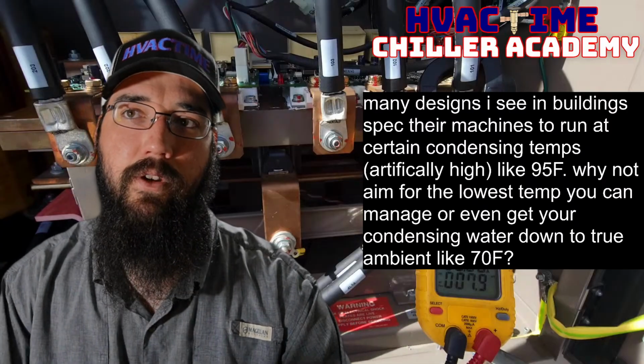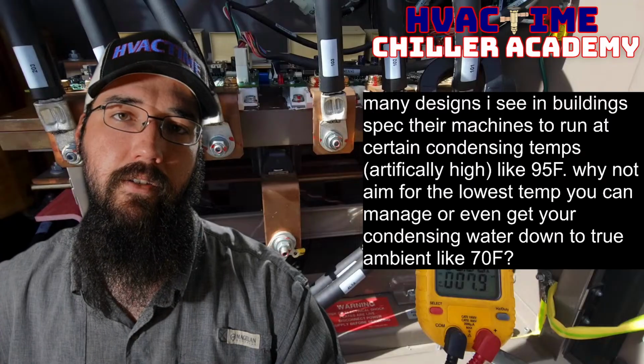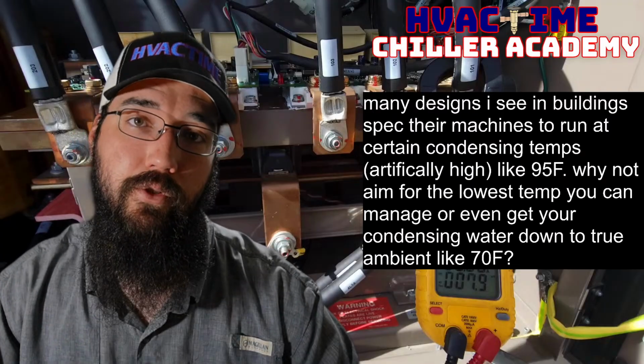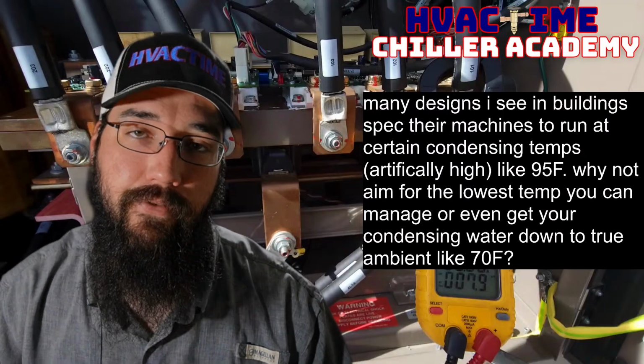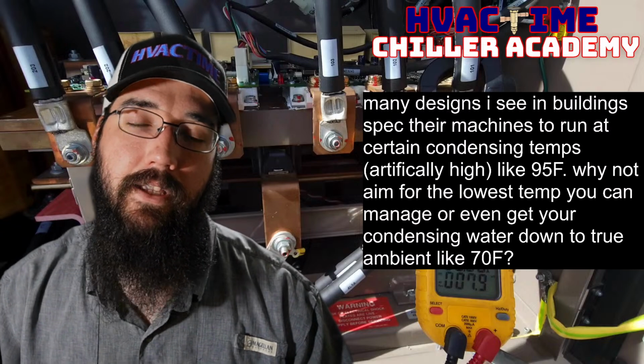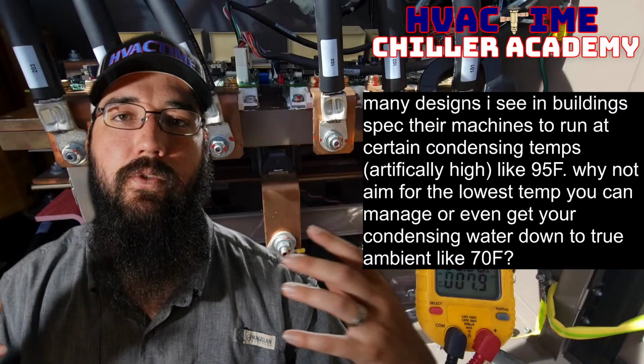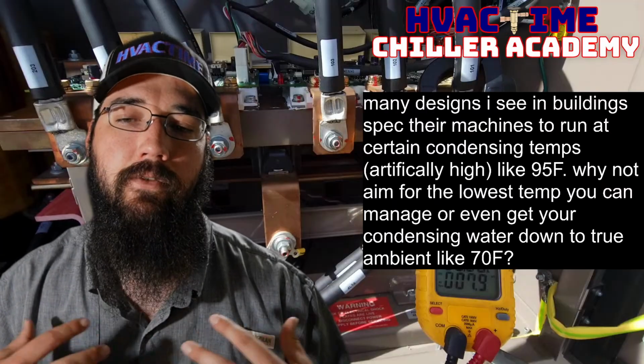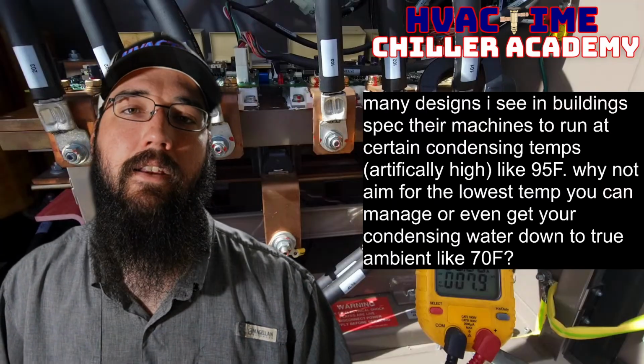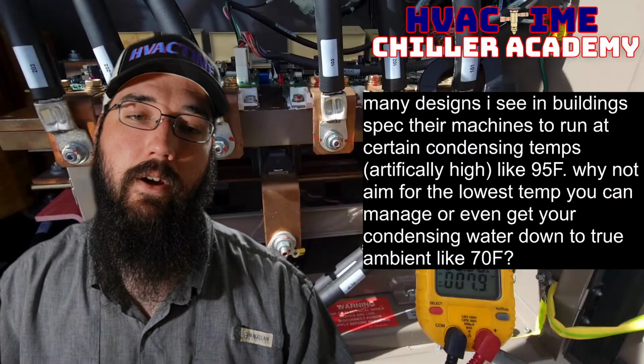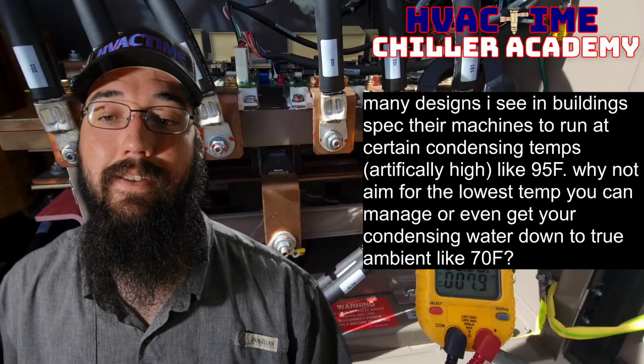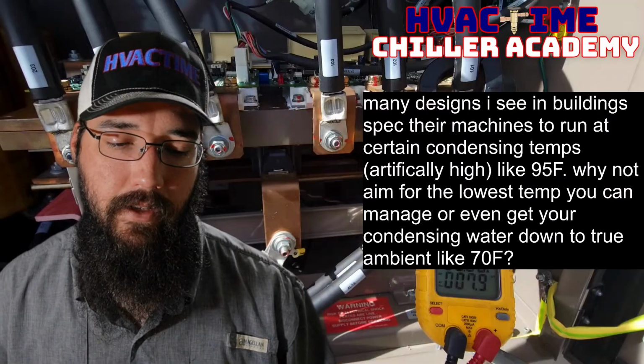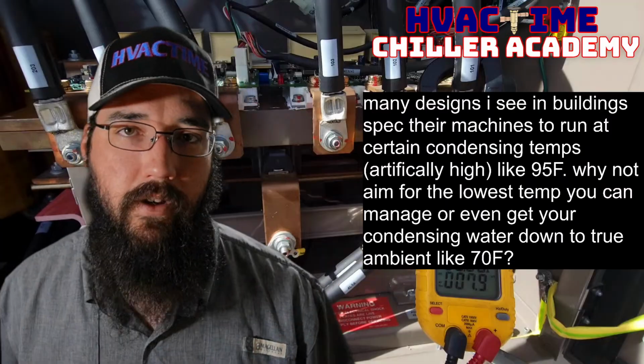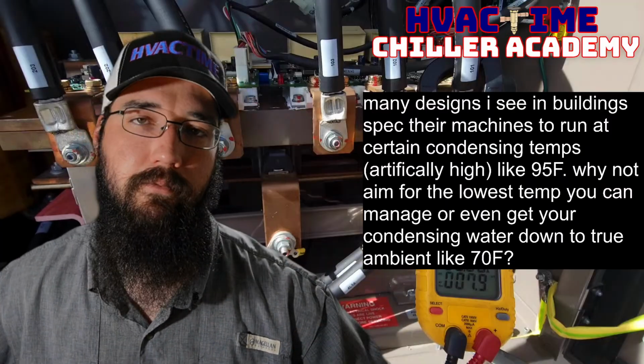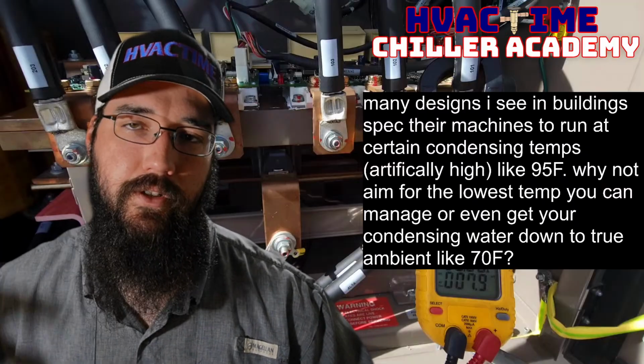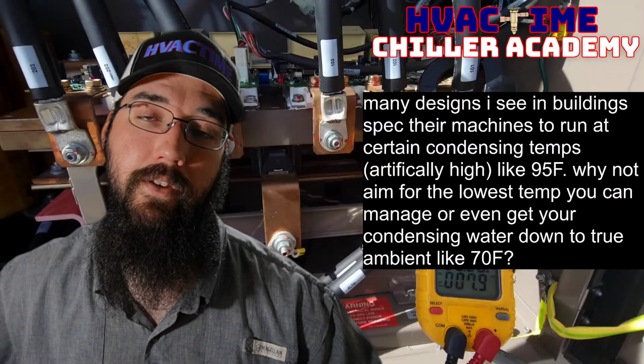And if they would have done a better job on the condenser water set point, they could have reduced that energy profile even further. But they don't see it that way because they're not chiller technicians. They don't see it from our perspective, and that's okay. That's their job, and this is ours. And this is why we have to work alongside people like this to help mitigate these little things. So, okay, I've gone on this whole spiel about set points and not artificially raising them. It's better to put load on the tower, not the chiller.